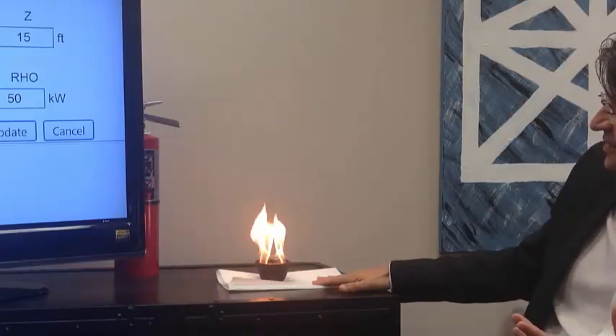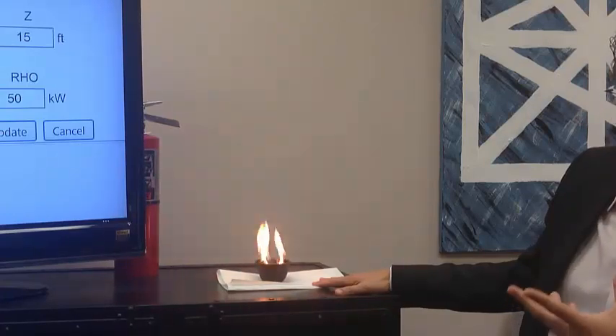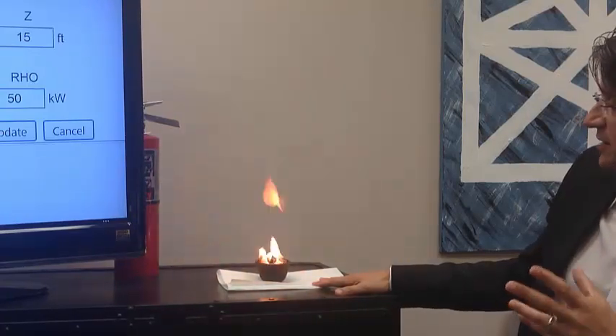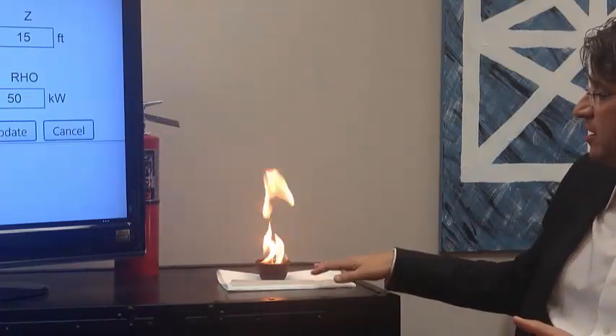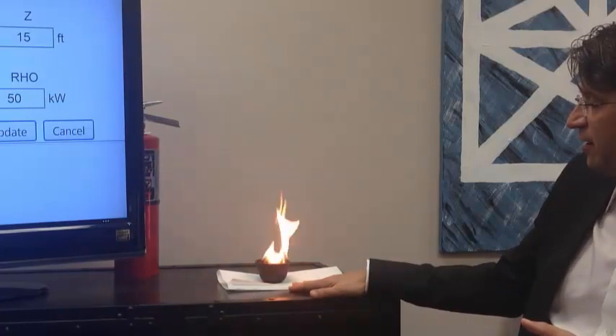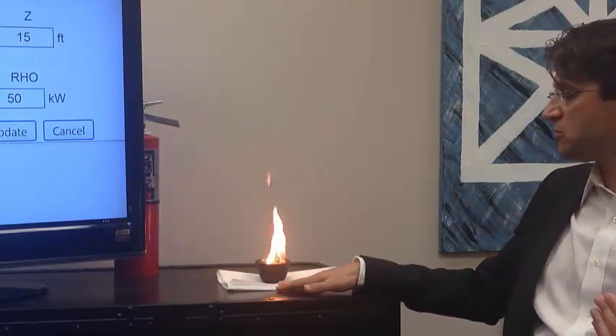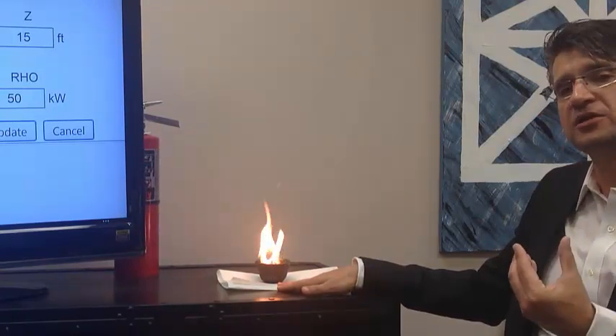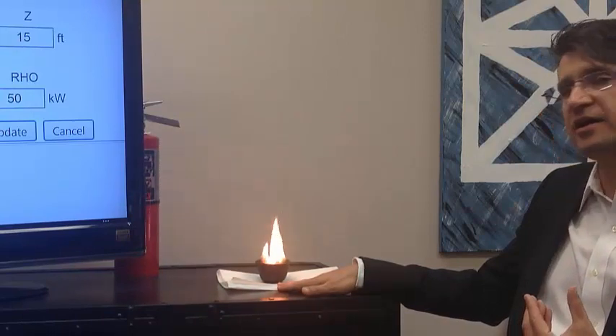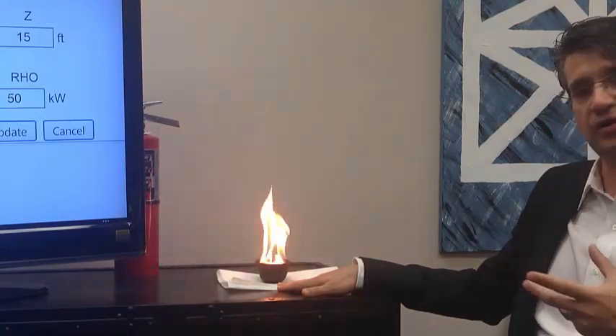So you'll see that this fire is actually substantially smaller than the fire that we're going to want to detect for medium sized zone. And the fire size that the equipment vendors are concerned with when they do that FM3260 test is a lot bigger than this. So this fire is relatively small and the fire detector is not going to be able to detect or see this fire from the same distance as is published in the vendor data, because the vendor data is based on a larger fire, a one foot by one foot pan fire that we're going to look at next.